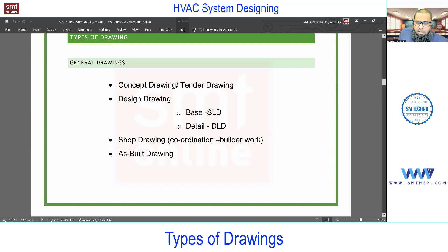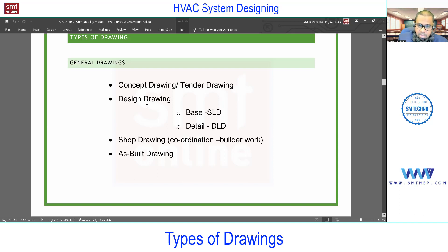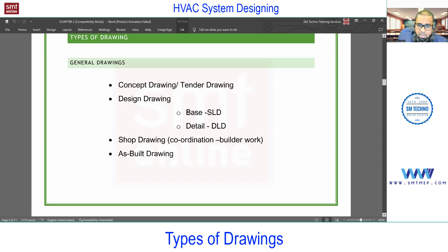The concept or tender drawing is a very initial stage drawing — you'll find just basic information, not much detail. Based on that, the design consultant will prepare design drawings, which contain more details compared to the concept drawing. In design drawings you'll find around 70 percent of the information required to complete the work on site. Within design drawings, there are base drawings and detail drawings — the base drawing uses single-line drawings and the detail drawing uses double-line drawings.